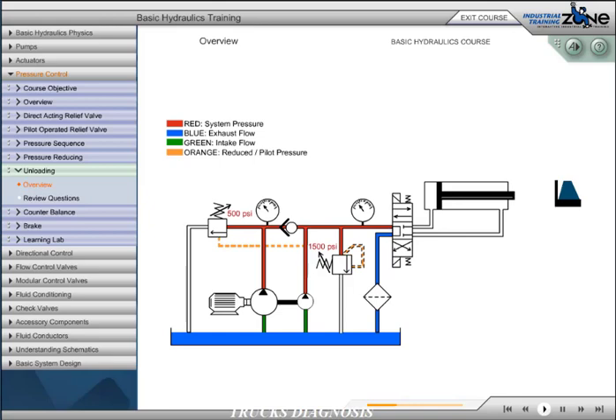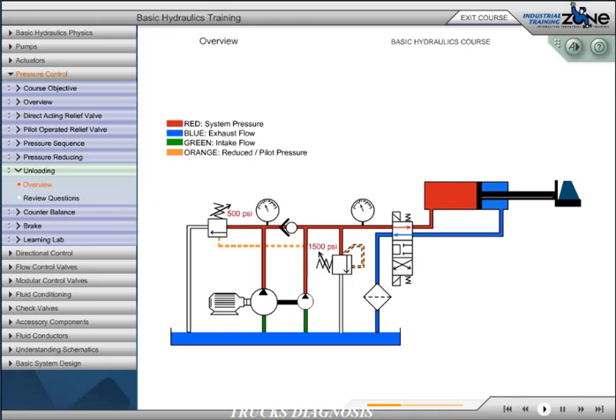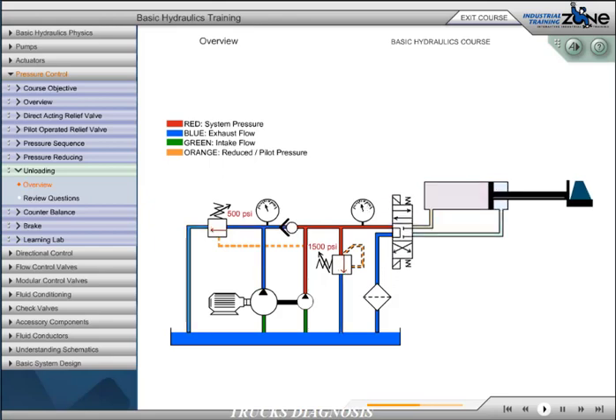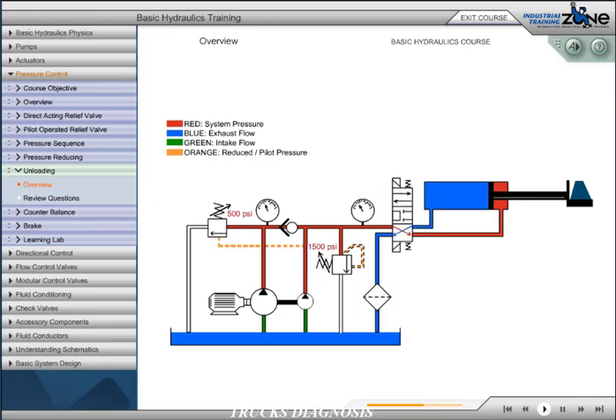If the pressure requirement is below the unloading valve setting, both pumps work together to provide a rapid approach to the load. At this point, the system pressure increases, thereby opening the unloading valve. The flow from the high-volume pump is directed back to tank at minimal pressure. The low-volume pump continues to deliver flow for the higher pressure requirement of the work cycle. Once the flow from the high-volume pump is unloaded, both pumps join once again for a rapid return of the cylinder. The high-low system requires less input power to meet the work cycle's speed and force requirements.